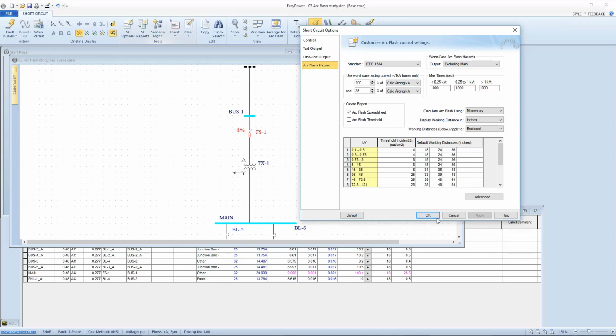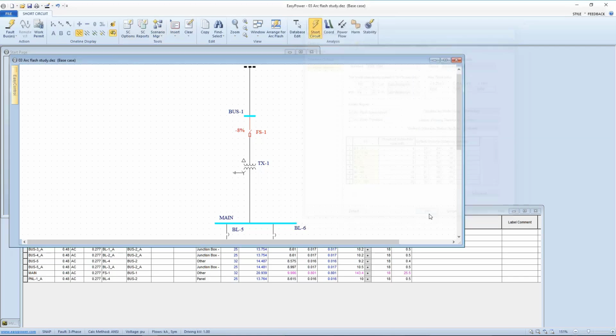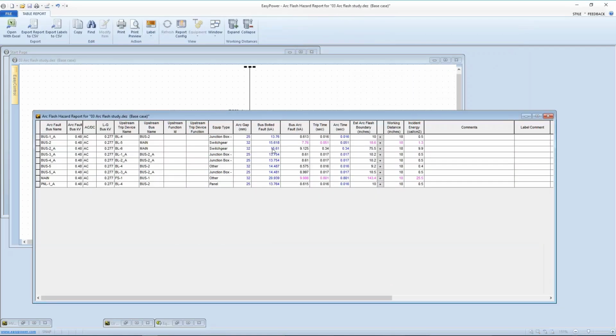And one of those recommendations is compare 100% arcing current with 85% arcing current and use whichever is worse for the incident energy calculations. As I look at the arc flash hazard report, that comparison is being made and reflected in the color of the type in my report. When I have dark type, the tool has selected 100% arcing current as the worst case. When the type is magenta or purple colored, then it's using the 85% arcing current, which is producing a worst case incident energy.